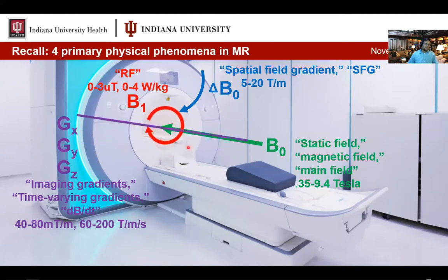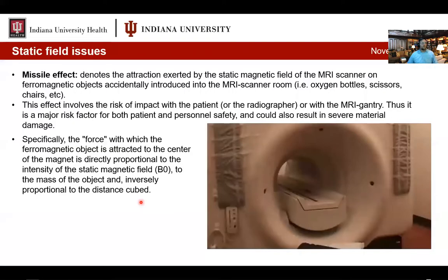But if you look at how fast it's changing, which you can see is changing very rapidly, that's the slew rate, which is measured at 60 to 200 Tesla per meter per second as the common levels. Static field issues, of course, include the missile effect. This is denoted as the attraction exerted by the main field of the MR scanner on ferromagnetic objects accidentally introduced into the MR scanner room. Most commonly, these are oxygen bottles, scissors, chairs. This represents a dramatic risk to the patient or the radiographer.